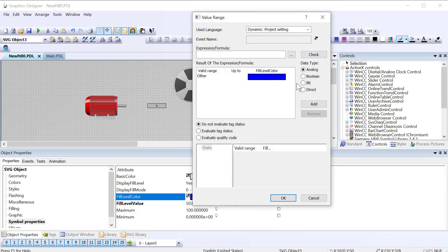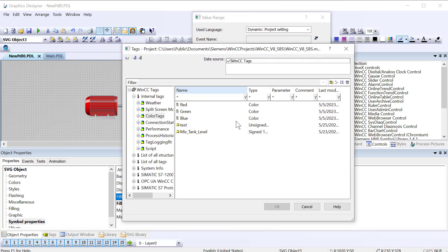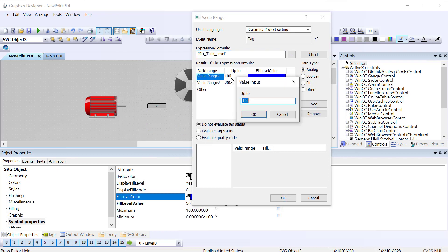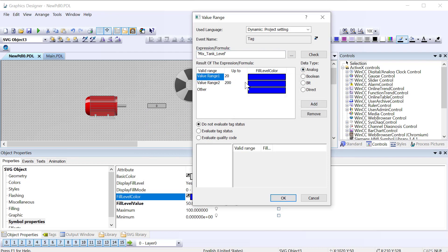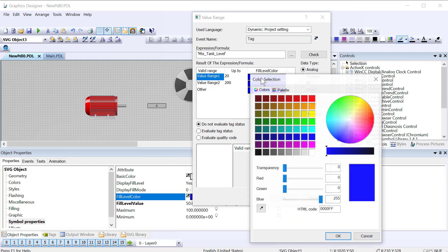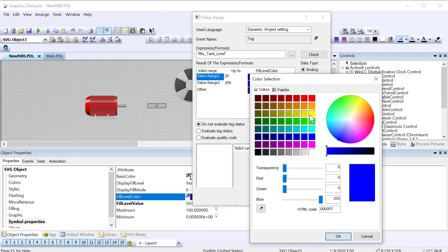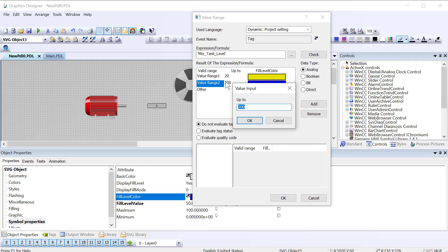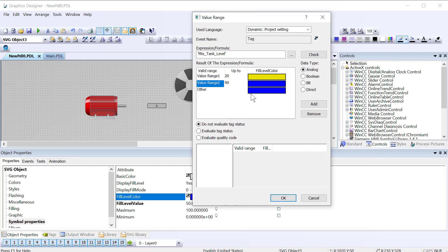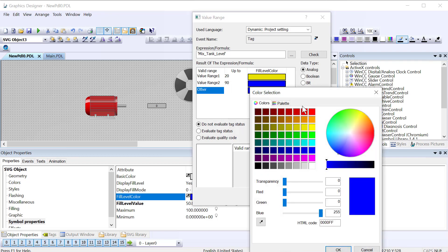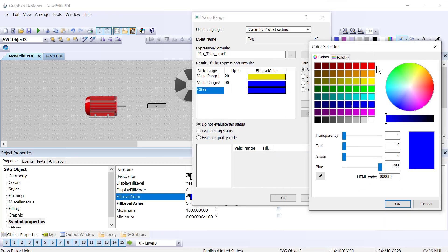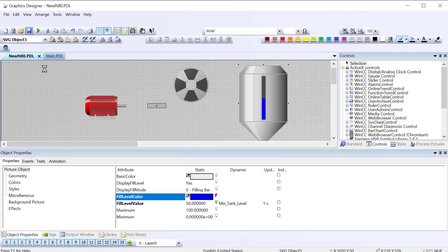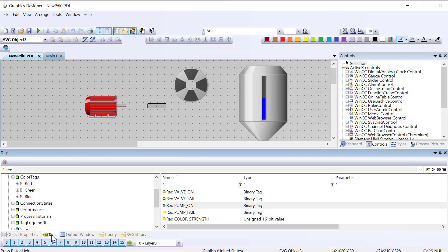So I'll use a dynamic dialog and in this case we're going to look at the tank level and I'm on analog so I'll just hit add a couple of times. I'll say up to 20, let's say that's too low so I want the fill color to be yellow, and then mid-range it will be blue all the way up to 90, and then anything over 90 will make red.